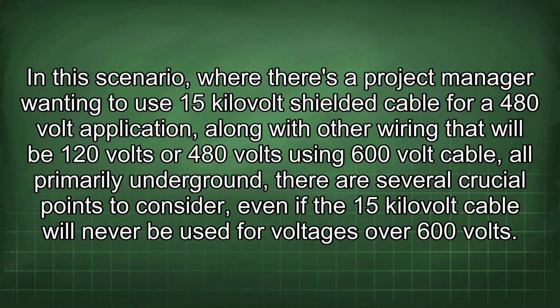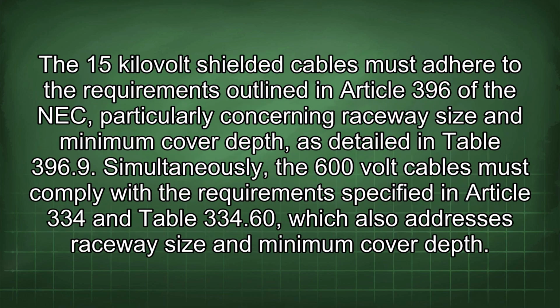In this scenario, where there's a project manager wanting to use 15 kV shielded cable for a 480 V application, along with other wiring that will be 120 volts or 480 volts using 600 V cable, all primarily underground, there are several crucial points to consider, even if the 15 kV cable will never be used for voltages over 600 volts. The 15 kV shielded cables must adhere to the requirements outlined in Article 396 of the NEC, particularly concerning raceway size and minimum cover depth, as detailed in Table 396.9.